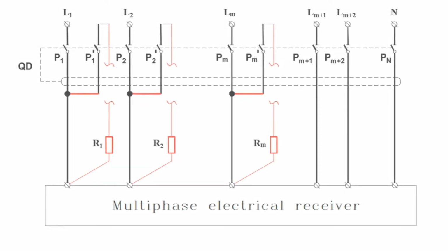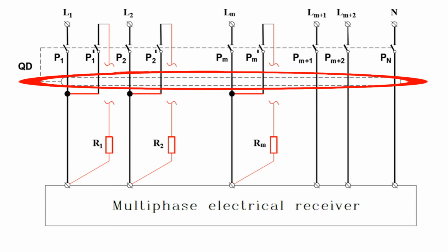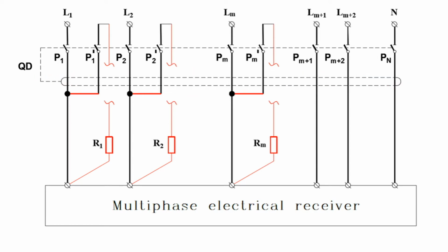The beneficial properties of this simple solution we shall now try to apply for the protection of single-phase and multi-phase systems. For this purpose, we combine several differential dipoles with a common differential sensor, for example, a transformer. It turns out that in such a combination, the dipoles do not interfere with each other in any way. Moreover, they perfectly coexist with separate poles. A variety of options is not limited. You can divide an even number of poles into dipoles, or you can divide a part among an odd number. They will work together and will not upset the balance of the differential sensor as long as the system remains closed and there are no damages to the connections.